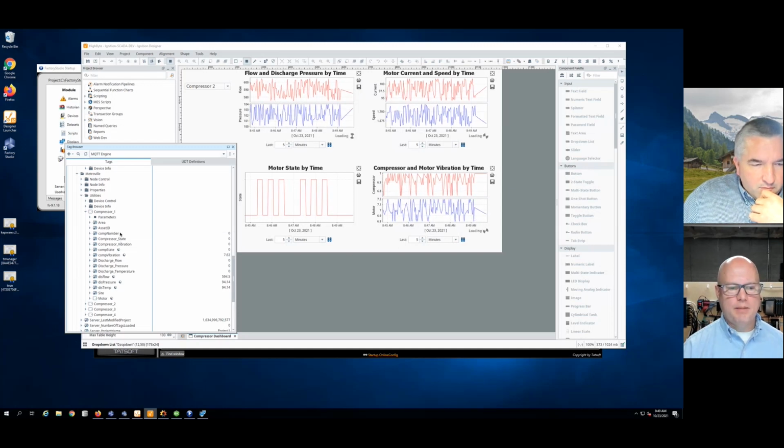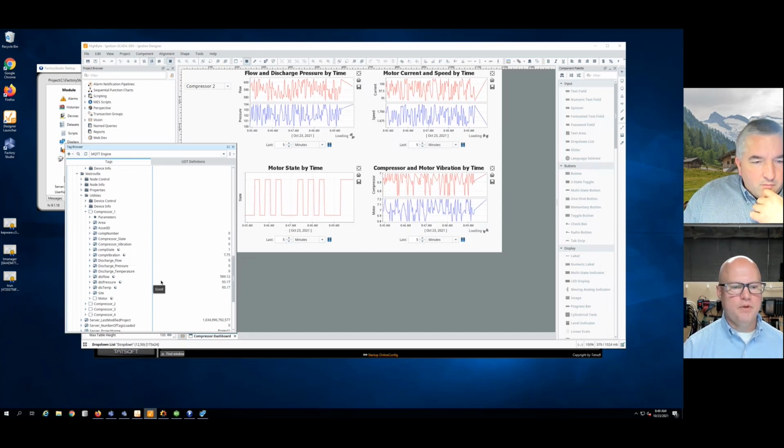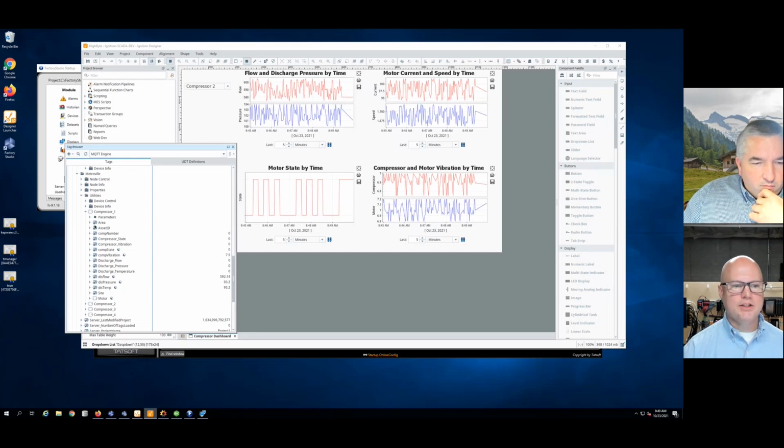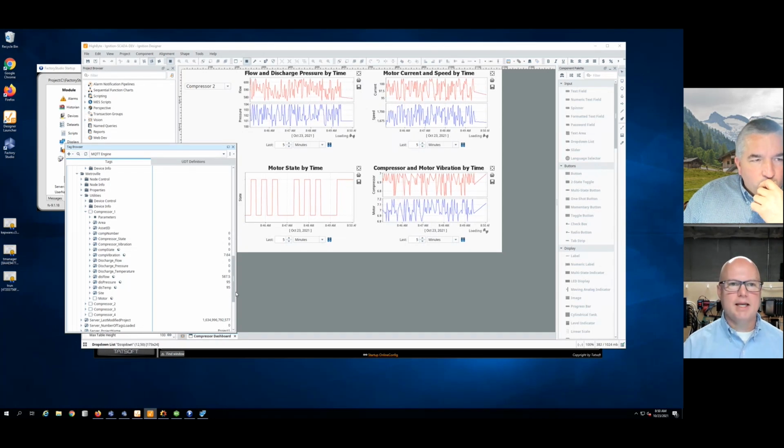And I think this, because I'm on a 9.1.18, this is a pre-release version. It looks like some of the data isn't getting fed through the way that it should. I believe that'll get taken care of in future. But you can see all that exact same information is getting published out as a UDT. So I don't have area and asset ID populated in this because I didn't build those specific tags. But you can see I'm able to see all of that.